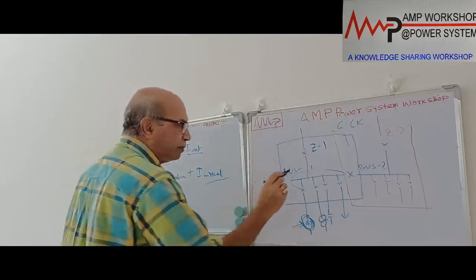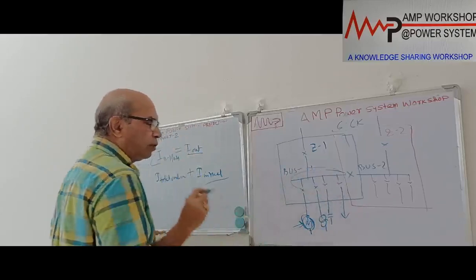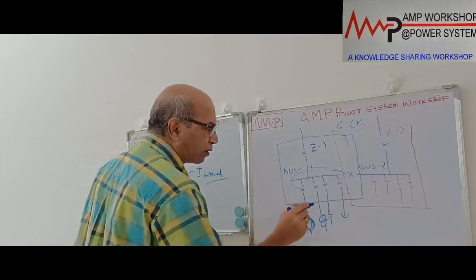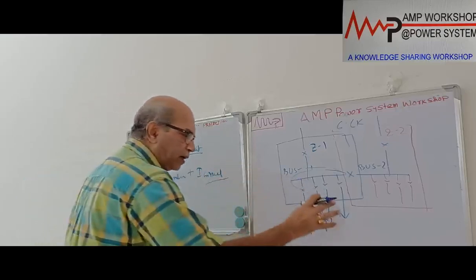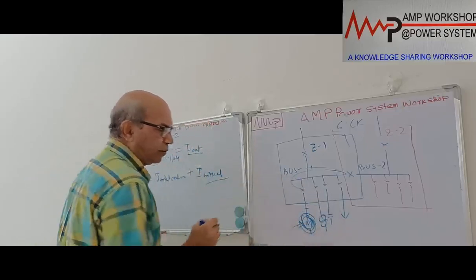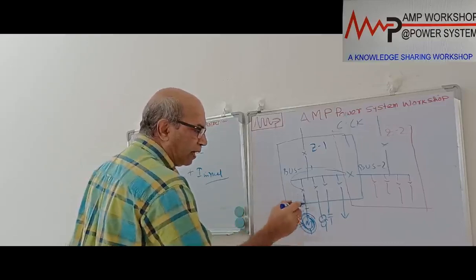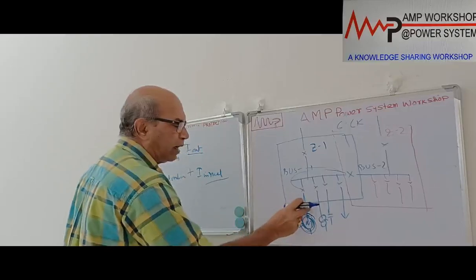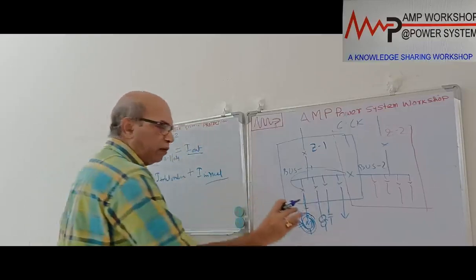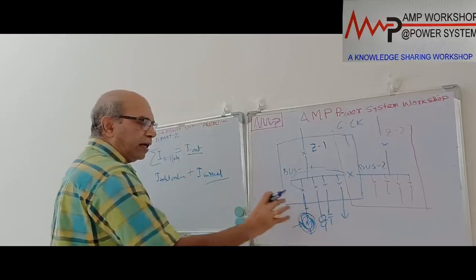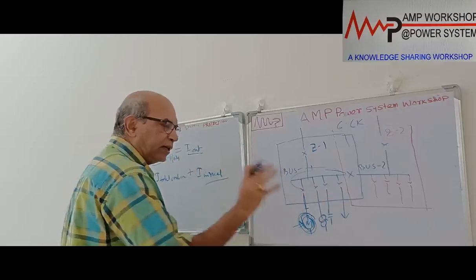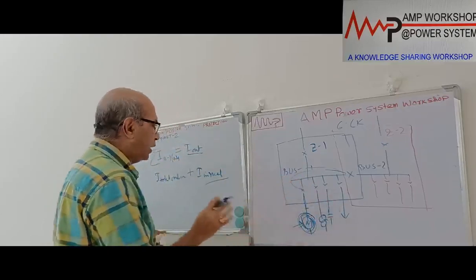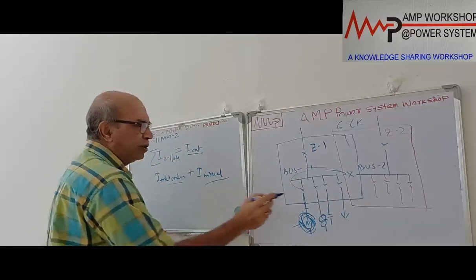When we consider this bus section 1 total current, the total current will be, except this feeder, all the other feeders which are normally running, that current, plus the starting current of this. When we consider the starting current, the running current of that particular biggest feeder will not be considered. All other feeders which are normally running for operation, that current plus this motor starting current will be the total current for this bus section.